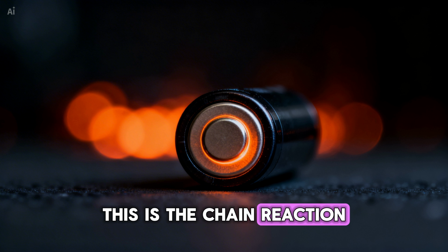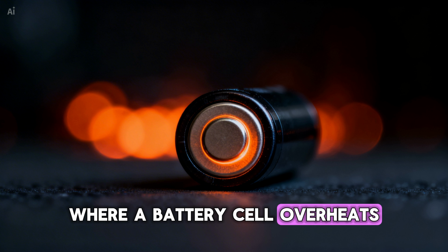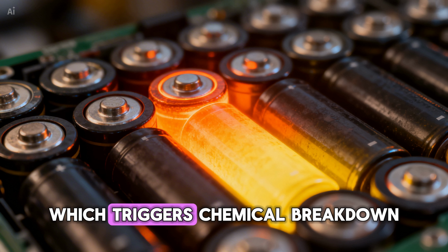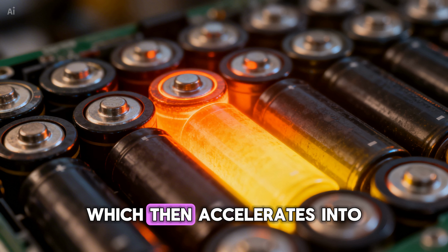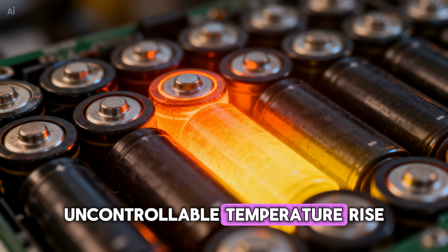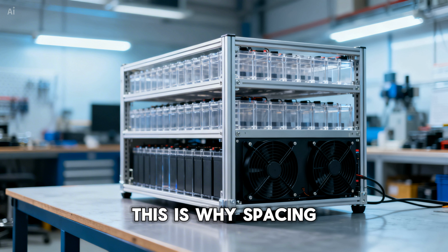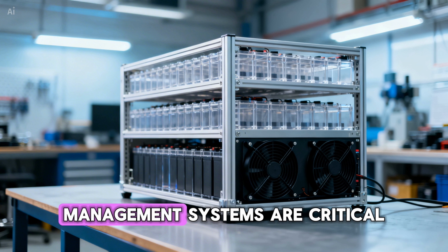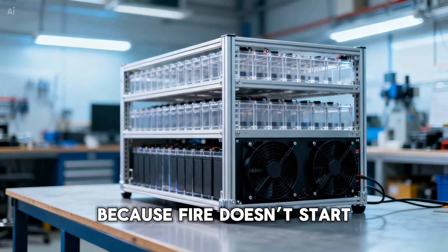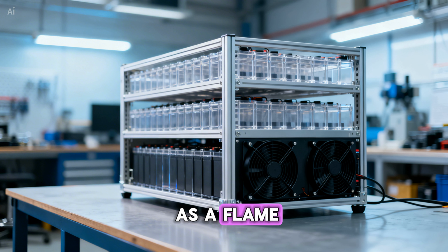This is the chain reaction where a battery cell overheats, which triggers more heat, which triggers chemical breakdown, which then accelerates into uncontrollable temperature rise. This is why spacing, cooling, and battery management systems are critical, because fire doesn't start as a flame. It starts as internal heat buildup.